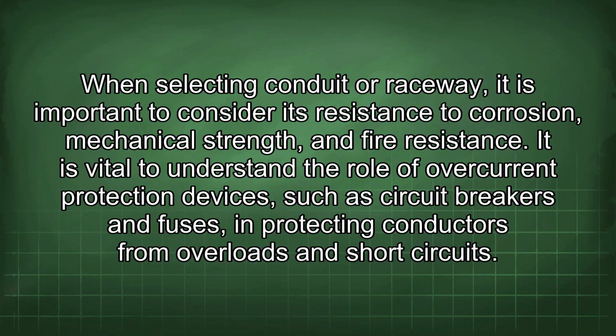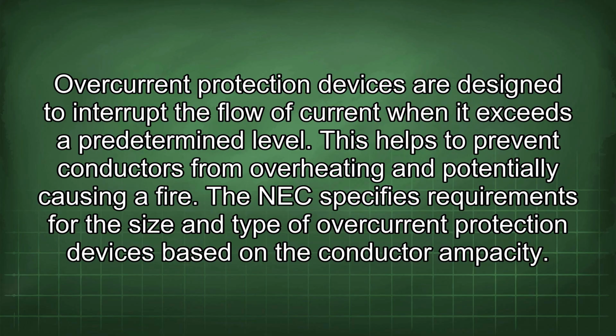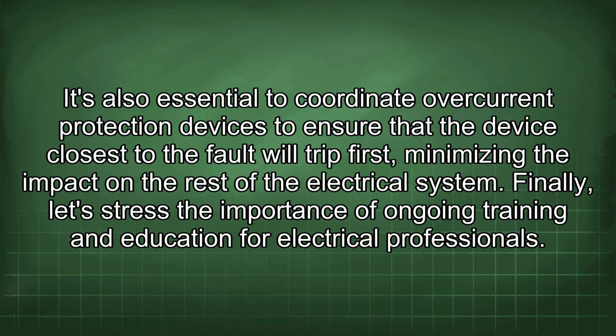It is vital to understand the role of overcurrent protection devices, such as circuit breakers and fuses, in protecting conductors from overloads and short circuits. Overcurrent protection devices are designed to interrupt the flow of current when it exceeds a predetermined level. This helps to prevent conductors from overheating and potentially causing a fire. The NEC specifies requirements for the size and type of overcurrent protection devices based on the conductor ampacity. It's also essential to coordinate overcurrent protection devices to ensure that the device closest to the fault will trip first, minimizing the impact on the rest of the electrical system.